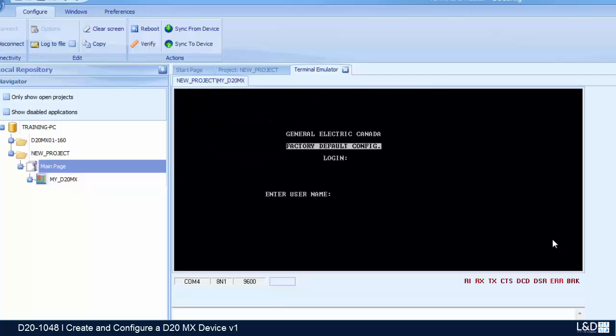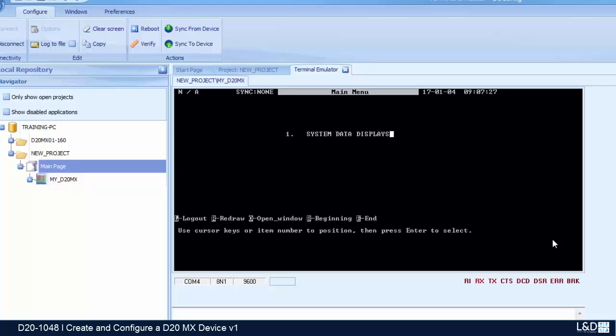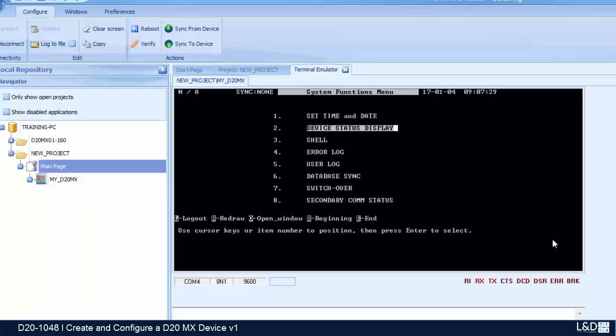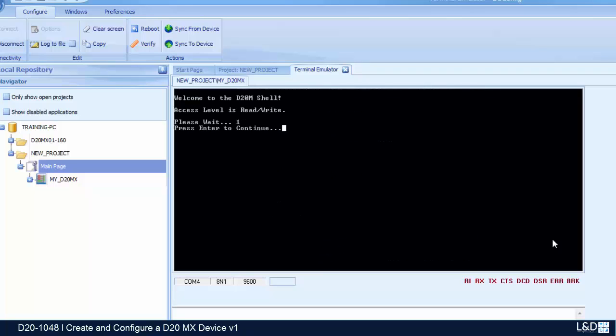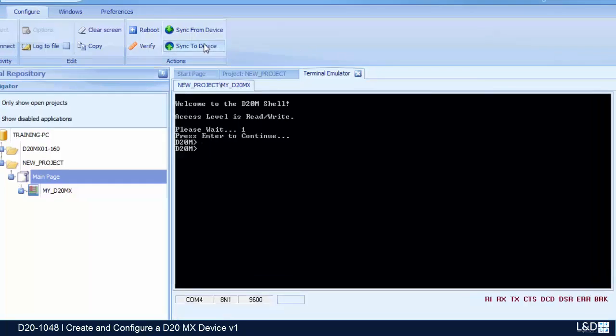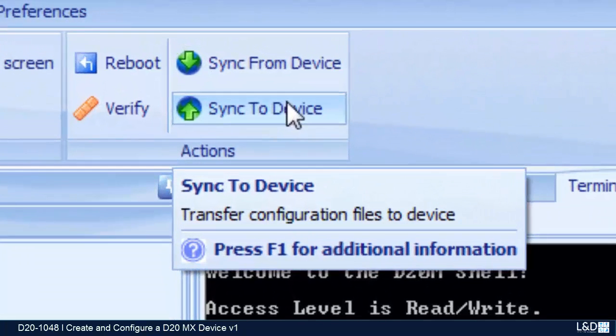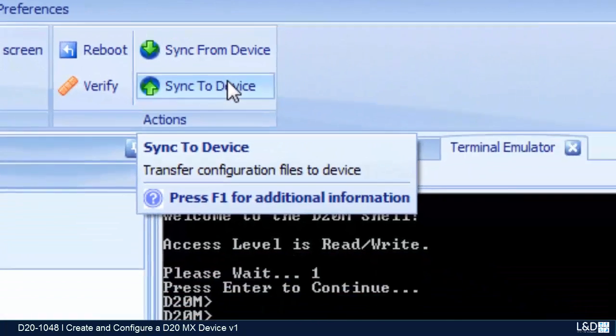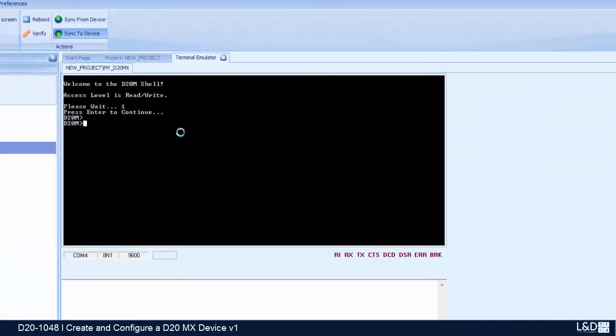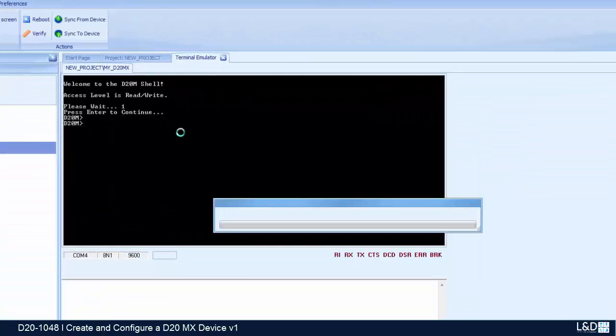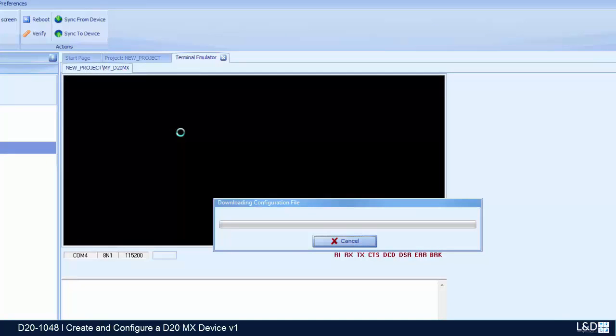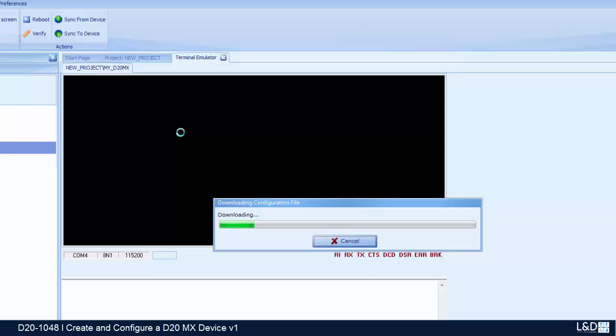At this time I've got the prompt. I'll put in the default name and password, login, go to the shell. And now I'm able to download my configuration, so I will click on the sync to device or press F7. The transfer of the configuration to the device will start. Of course, because we checked the high baud rate of download, it's downloading at 115,200.